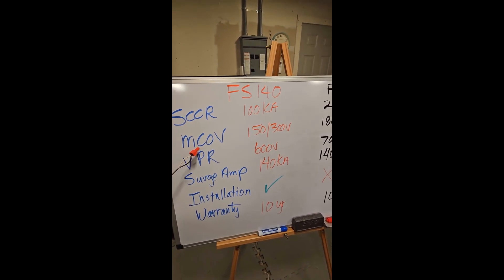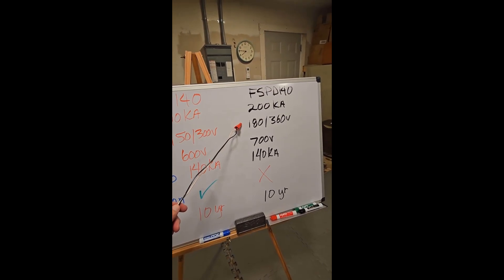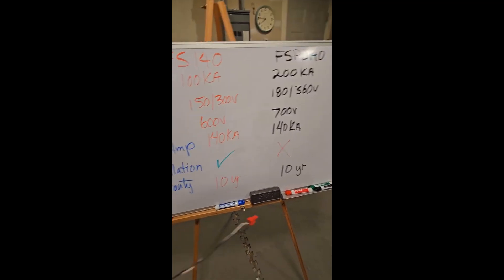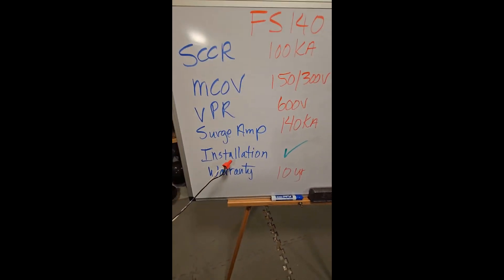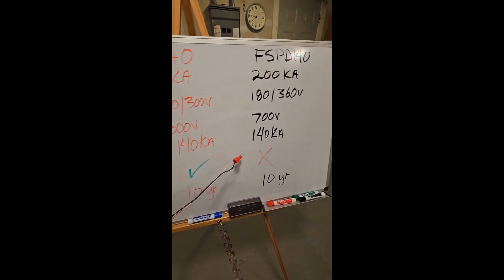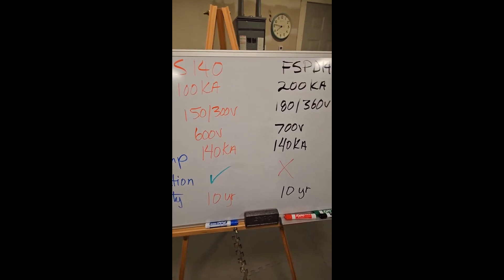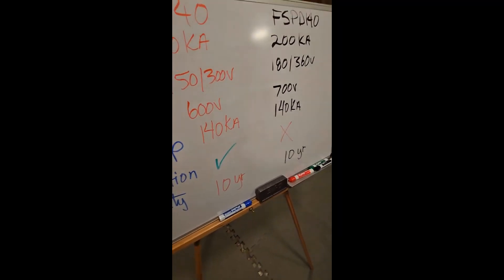Operating voltage: the FS-140 is a lower voltage, which is better than the FSPD. Voltage protection rating is also lower on the FS-140 than the FSPD. The surge amp ratings are the same. The FS-140 is definitely more installation friendly than the FSPD. The warranty is the same on both. Right now the price between these is also very similar as far as availability.